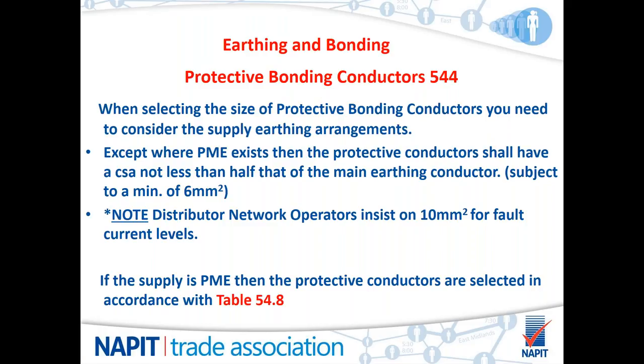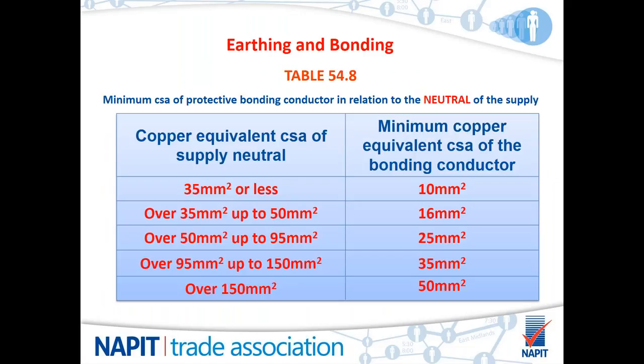If the supply is a PME, then all protective conductors are selected in accordance with table 54.8. So, as Paul mentioned, here's table 54.8, which shows you the minimum cross-sectional area of bonding conductors in relation to the cross-sectional area of the supply neutral. So if you were to have a supply neutral of 35 mil or less, your bonding conductor would be 10 mil.